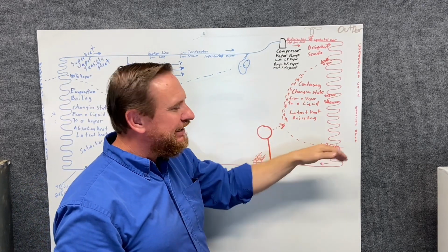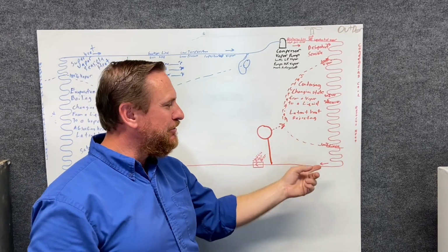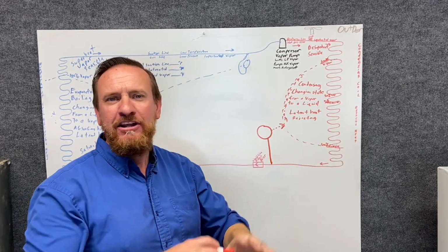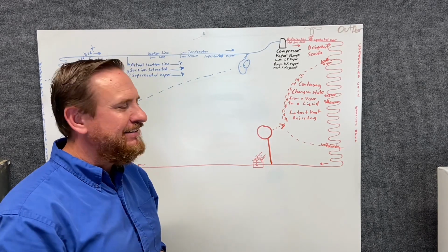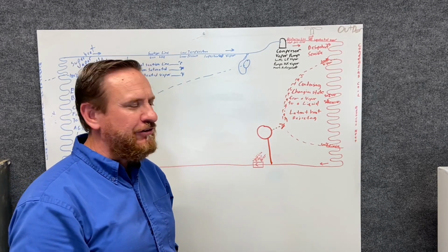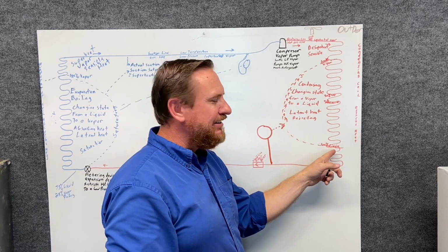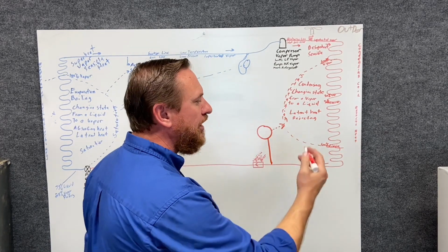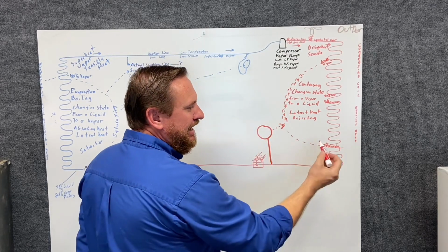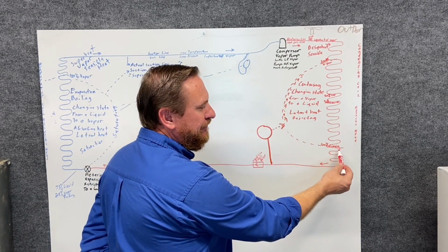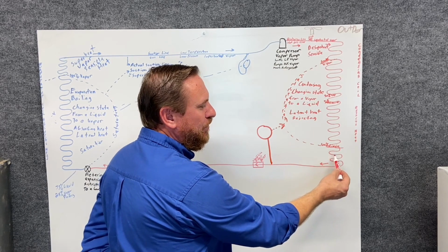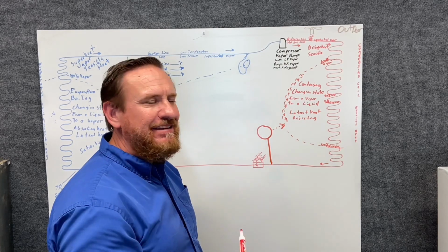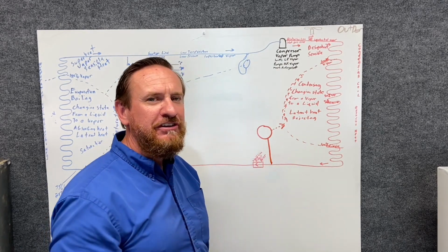Now, after it's completely changed into a liquid, that liquid temperature is still going to be at 115 degrees Fahrenheit at 100 degree outdoor air. Just throwing some random numbers to give you an idea. That's still going to have a heat transfer. The difference is now the heat's going to leave the refrigerant and go to the air, but the refrigerant will start to cool off. It will cool off below its saturation point. If it's 115, then it goes to 114, 113, 112, 111, 110. It's actually changing in temperature, and we can measure this, so this is sensible heat.